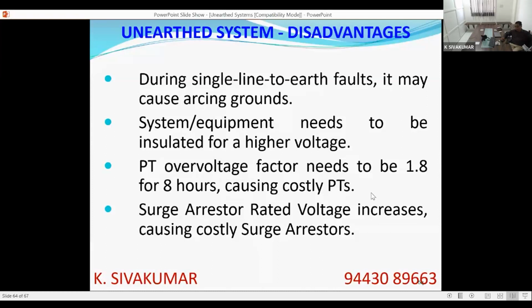Similarly, when you see the PT standard, the potential transformer standard, the overvoltage factor is very low for grounded systems. For a solidly earthed system, it is 1.2 continuous and 1.5 for 30 seconds. If you see the unearthed system, it is 1.2 continuous and 1.8 for 8 hours. So if you order a PT with a higher overvoltage factor, it has to withstand 1.8 times the rated voltage for 8 hours. Definitely the PT will be bulky and costly. If you want to use the PT in an unearthed system, you must go for an overvoltage factor of 1.8 for 8 hours.